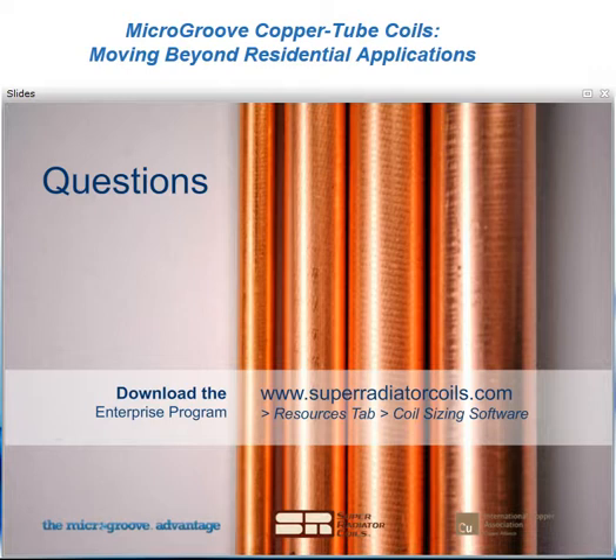Alrighty. Next one up: is the 5mm product only offered with grooved tubing? No. The grooving is an important benefit, and I think John highlighted how the grooving can increase heat transfer performance, particularly for refrigerant. But we do have smooth wall tubing available, and it lends itself to certain applications, water applications. We've been focusing really heavily on refrigerant applications, but for water coils, particularly clean water coils, you have to worry about fouling otherwise. A smooth tube may be most beneficial.